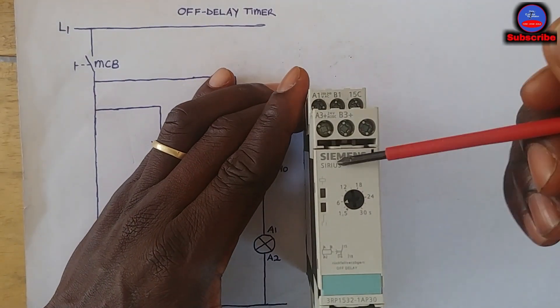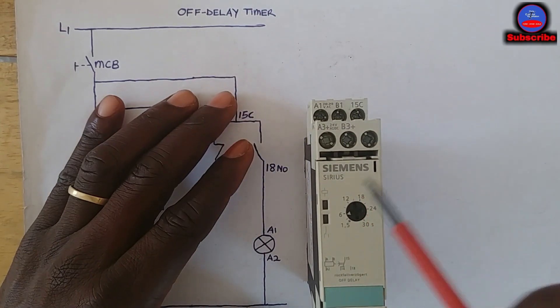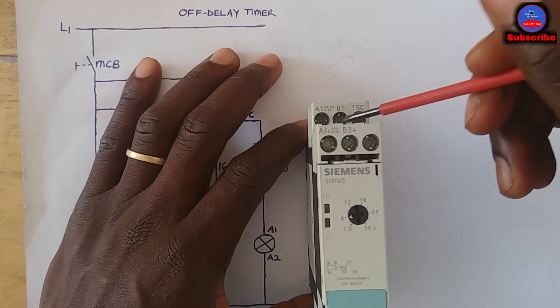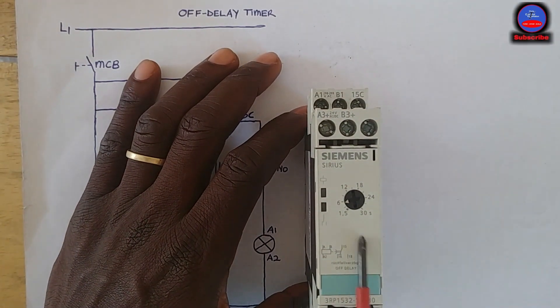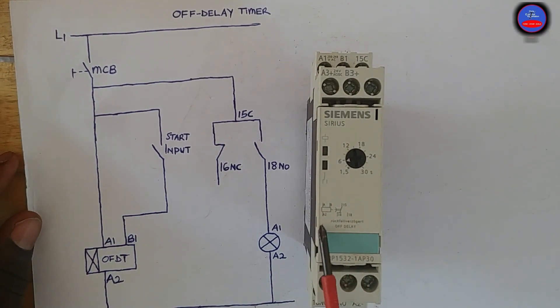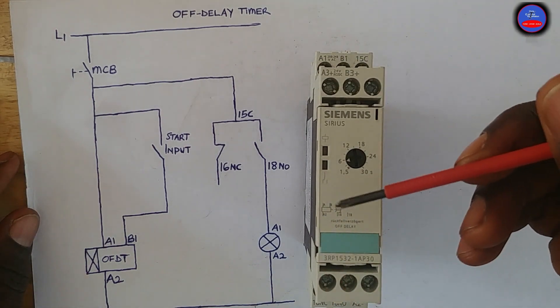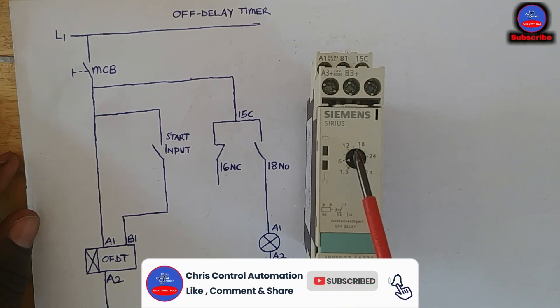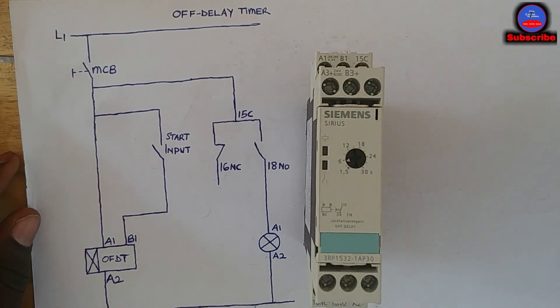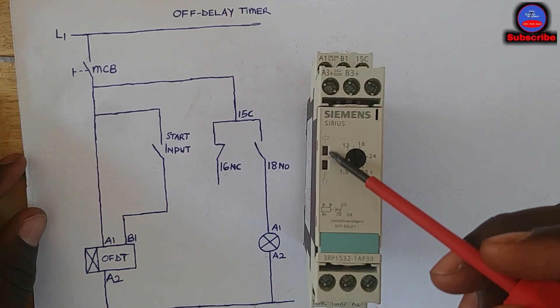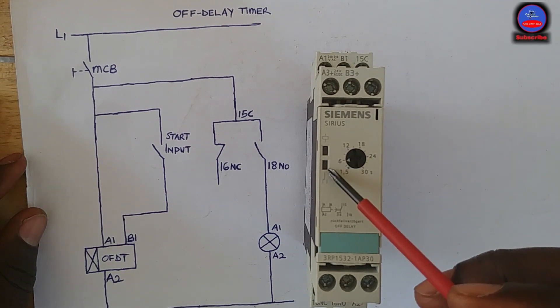B3 is the initiating input terminal for the DC side, and B1 is the initiating input terminal for the AC side. The diagram shows A2 at the bottom, the timer contacts, and the potentiometer used to set the timer time. This timer ranges from 1.5 to 30 seconds. There is also a power light and a contact light.